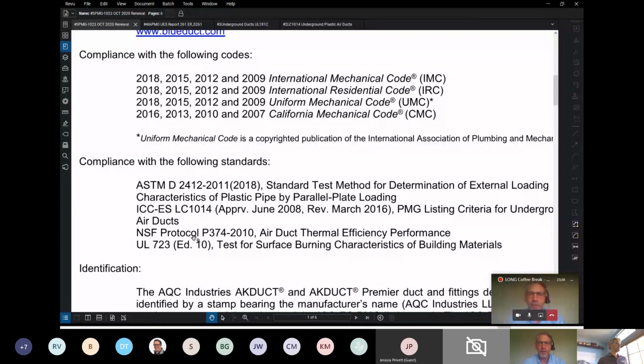This is interesting, and it's nice for the engineer, because the NSF 374 protocol is a much more realistic test for understanding the thermal performance of the duct, unlike the ASTM test which is a static state test — this is how they test your insulation and get your R value. They put the insulation in a test chamber where the air isn't moving, so you don't have conduction or convection. They measure how long it takes for the delta T to occur to get your R value or K value. But that's not relative to ductwork.